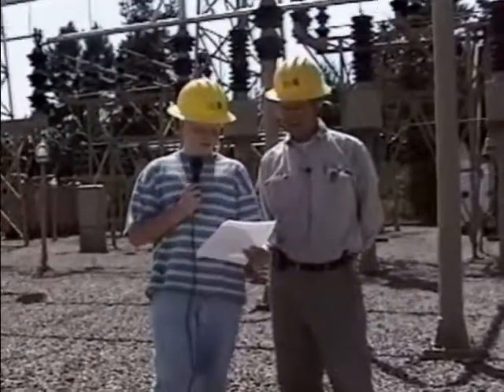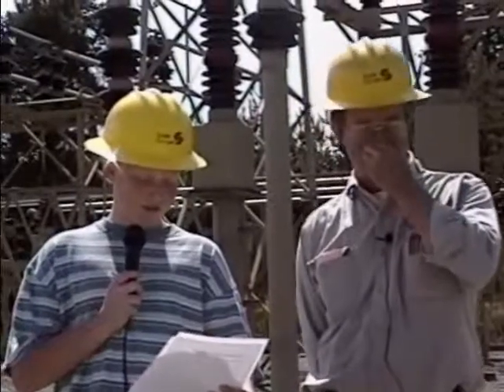How much power can a transformer handle before it gets too hot? Well, that varies. A transformer has a rating of how much power it can handle, and it varies depending on which cooling devices are in effect. Like this transformer here, it'll handle a certain amount of power without the fans going. With the fans going, it'll cool down more and can handle more power. Other transformers in other places can be water cooled, or what they call forced oil cooled. There are several devices for making them handle more power.